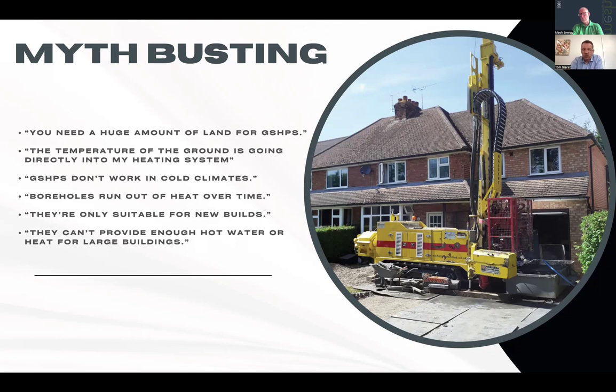Also, with a ground source heat pump, depending on how many people will occupy the house, how large the property is, and how many bathrooms there are, we will normally oversize the hot water cylinder to give you more capacity in the cylinder for the hot water. That's how you can compensate for the slightly lower water temperature in the hot water cylinder.